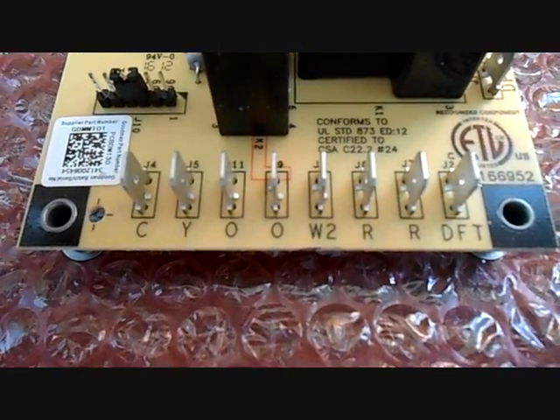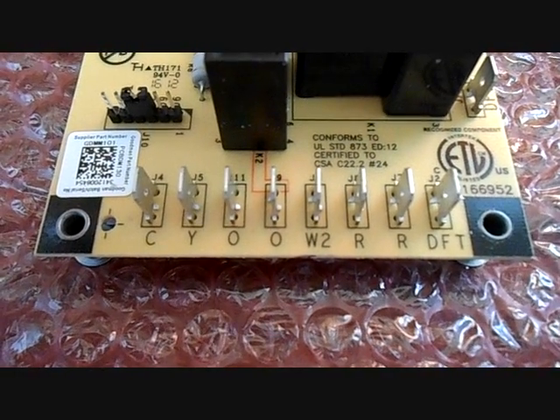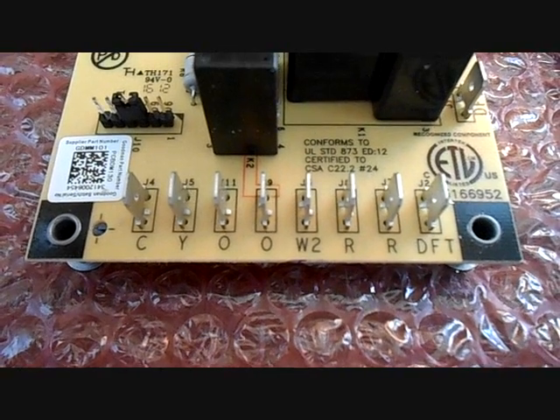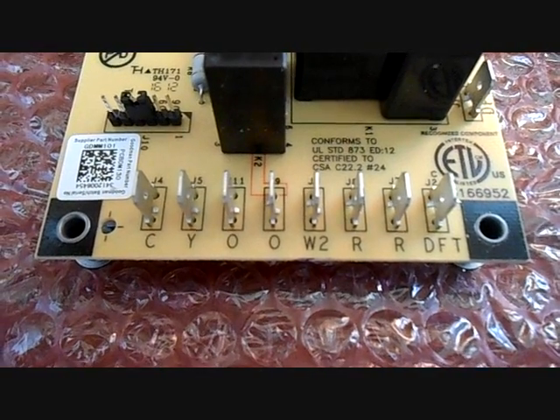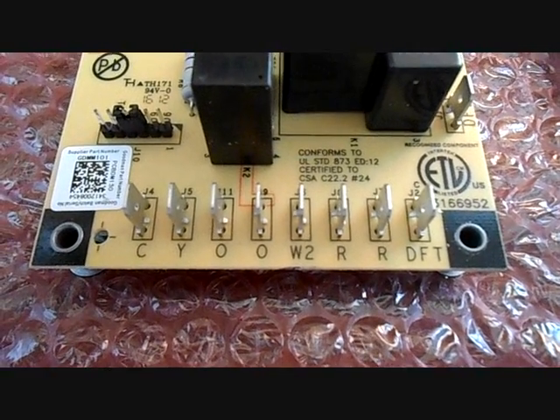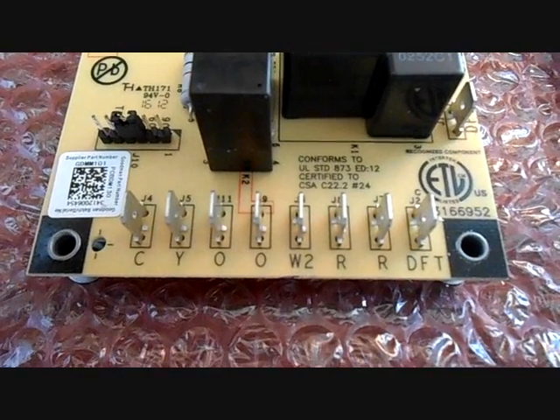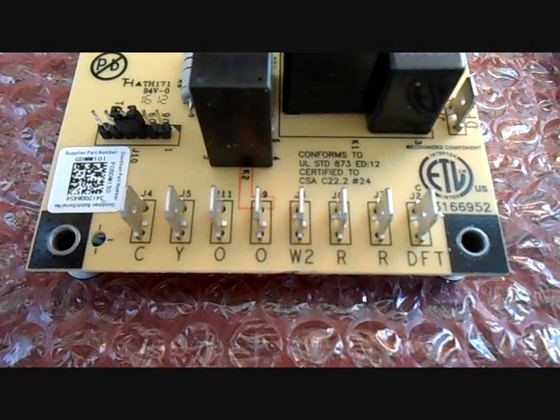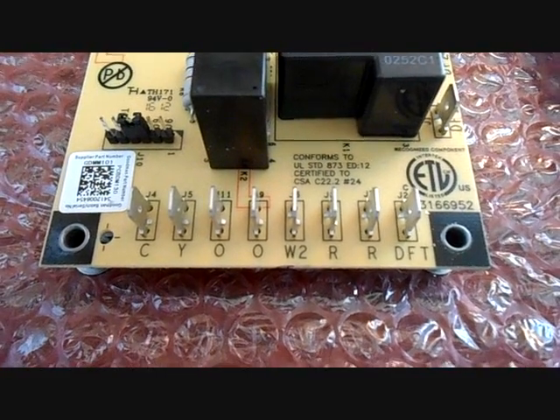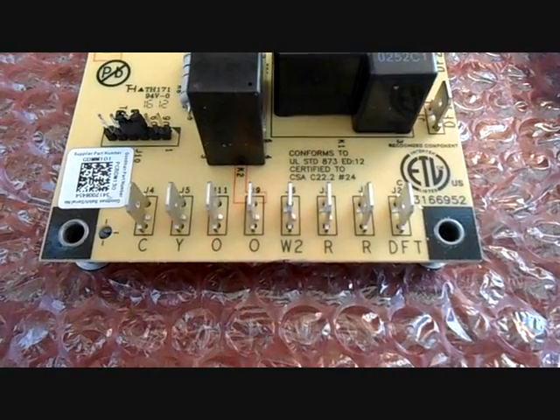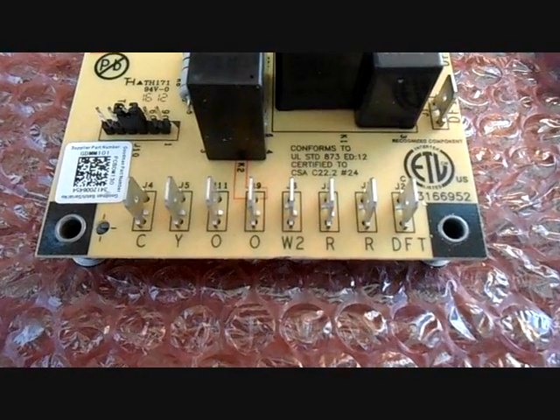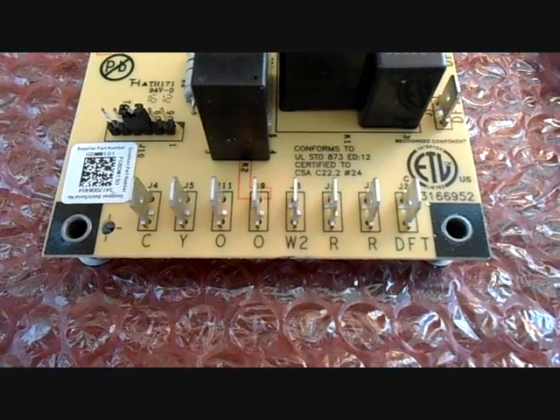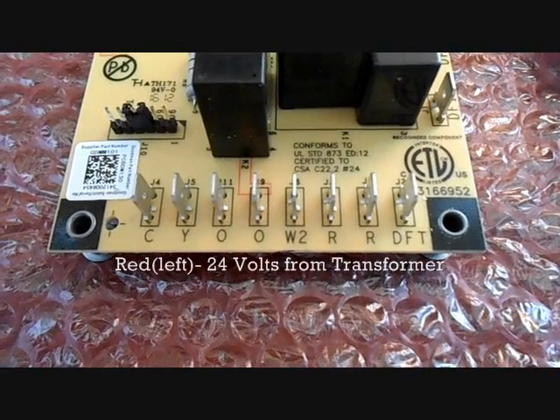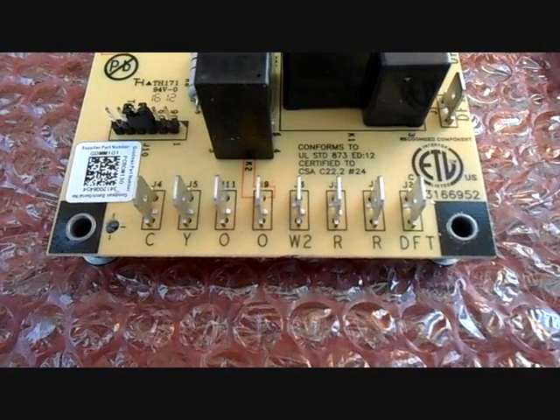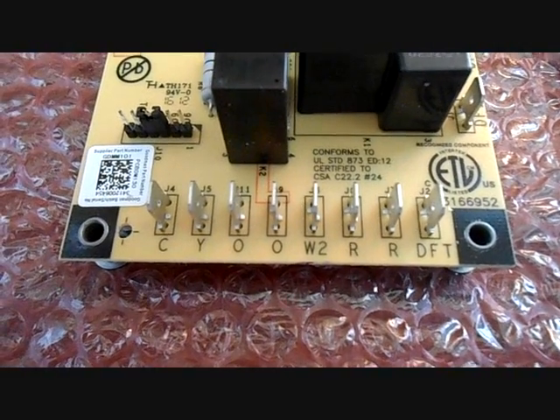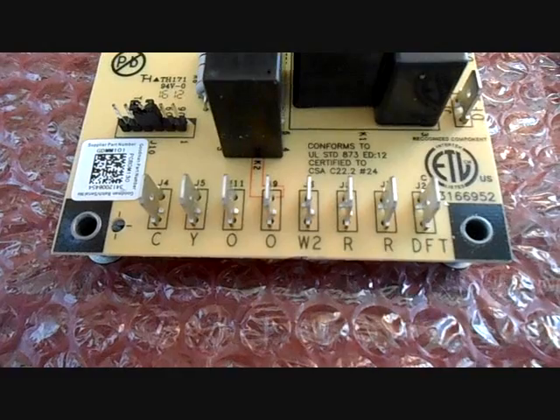Across the base of the board, you see there are several wiring designations from left to right, and these are all low voltage wires. You have C is common, Y is your contactor. You have two O's, that's your reversing valve wires. One goes to the valve, one comes in from the thermostat. W2, that's your heat strip wire. When your defrost controller sends the unit into defrost, you'll have a 24 volt signal heading out to your heat strips from there. You have two R terminals. It's just red terminals. One of them is the red 24 volt signal coming into the defrost board from the thermostat. And one of the terminals, the one on the right, exits to the defrost thermostat and then returns on your DFT. That's defrost thermostat wire.